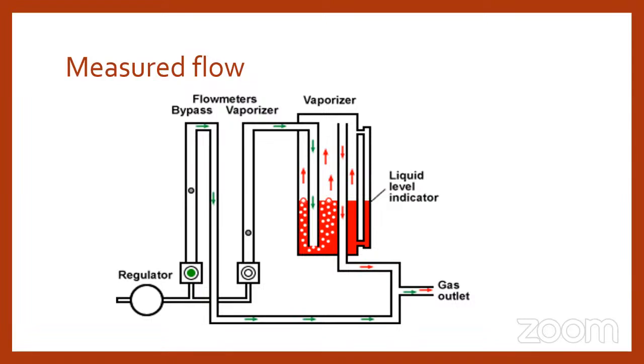If we open this white knob that is present in the second line, then some amount of the gas enters the vaporizer, and it will bubble through the liquid that is present in the vaporizer and mix with the anesthetic agent and enter the system. At the outlet, both of these gases will mix with each other and be delivered to the patient. And we have a regulator to monitor and regulate the concentration that can be flowed through the system.